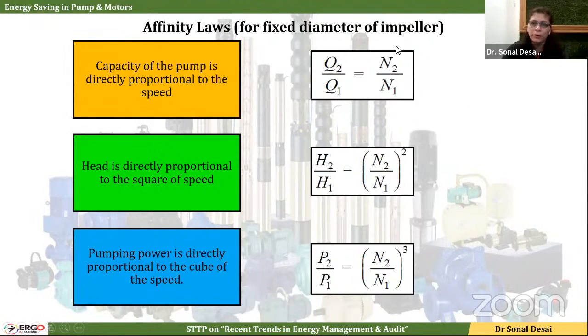So whenever we are talking of pump performance, we have to see what the speed is. If speed increases, flow will increase and head will increase. If speed decreases, these parameters will decrease. But the decrement will not be in direct proportion. They will be in proportion to the square for head, and power is in proportion to the power 3 when we talk of speed being reduced.